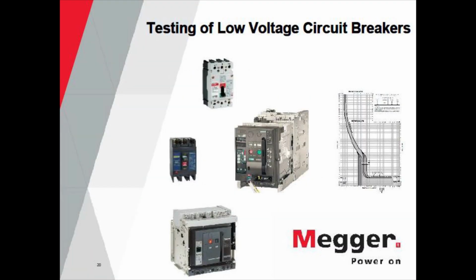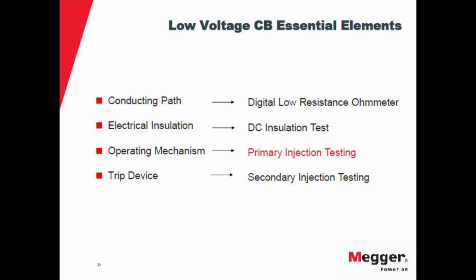So, low voltage circuit breakers. You mentioned the switchgears. I don't know if you also do low voltage circuit breakers. For these, this is the full spectrum of tests that you perform. Depending on the breaker, you would do one more test, which is the trip device with secondary injection. For the conducting path, we just talked about the digital low resistance ohm meter. You can perform the electrical insulation DC test, the famous Megger test. We're not supposed to use that Megger for the test, but that's how the industry handles it. For the operating mechanism, we do primary injection testing, and that's what we're going to talk about in this section of the presentation.